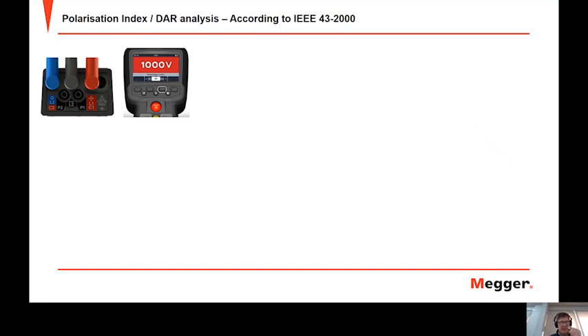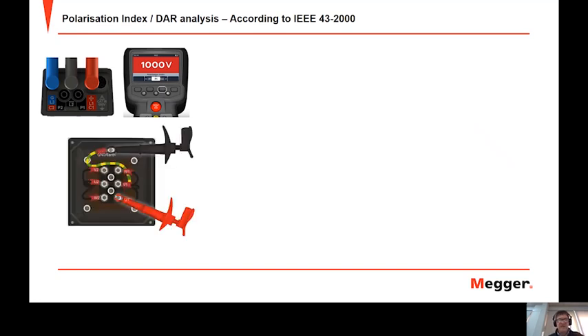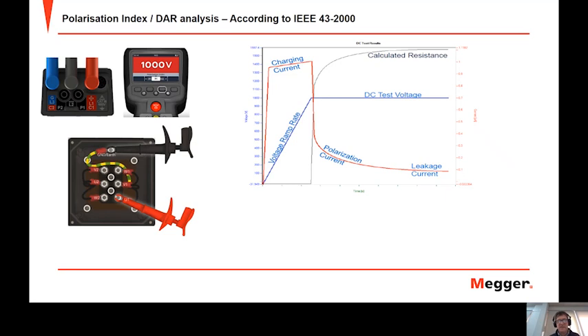The PI test is generally performed only on high voltage machines, and it's a 10-minute IR test. We take the 10-minute IR value, we divide it by the 1-minute IR value, and that gives us the PI ratio. Typically, the PI ratio should be greater than 2, but the standards again cover that depending on the type of insulation, and sometimes the location of the motor. If it's a very difficult environment, then customers may accept a lower PI ratio based on their experience.